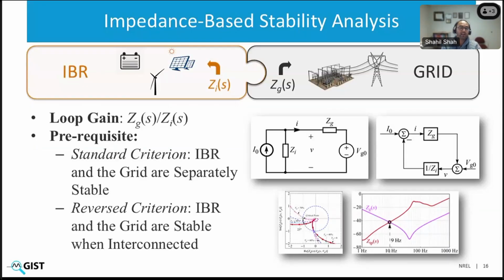let me give a high-level overview of what the impedance-based stability analysis method is. As you can see on the top, we can represent the IBR by its impedance, ZI, and the grid by its impedance, ZG. In impedance-based stability analysis, we just need the impedance response of the IBR and the grid to understand if they are interoperable, or if they are stable together or not. These impedance responses can be obtained from EMT models, from field measurements, or directly from experimental measurements.